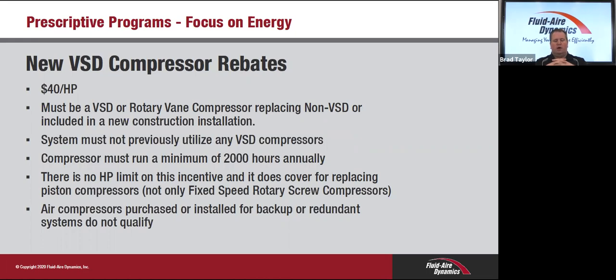So when we're talking about prescriptive, and Laura will help me out here, the most obvious is variable speed type compressors. It's a flat rate of $40 per horsepower, and it must be replacing a fixed speed type compressor or non-variable speed. But it can also be used in new installations as well. System must not previously have variable speed drive installed, meaning if you have one already and it failed, this type of incentive does not cover replacement of existing variable speed drive compressors.